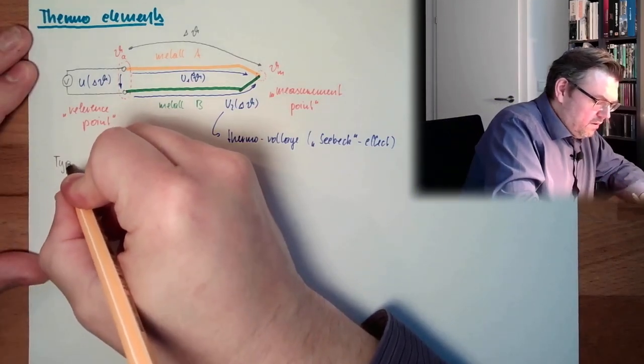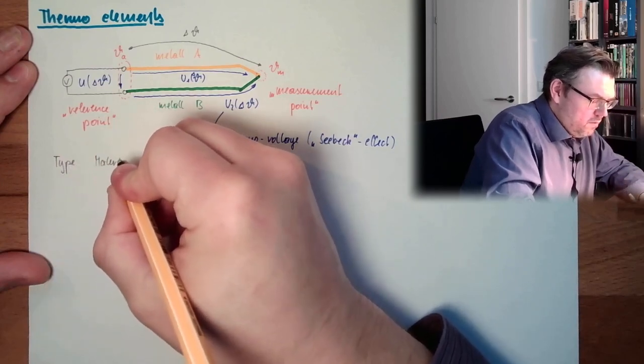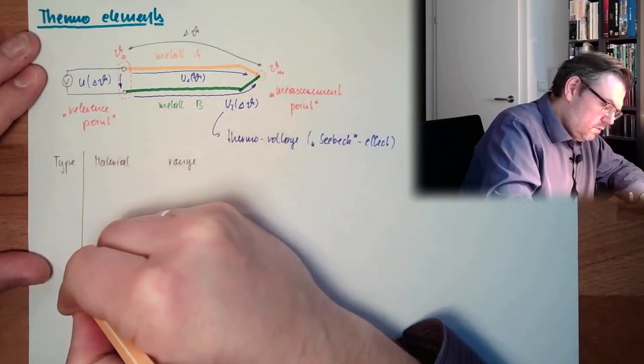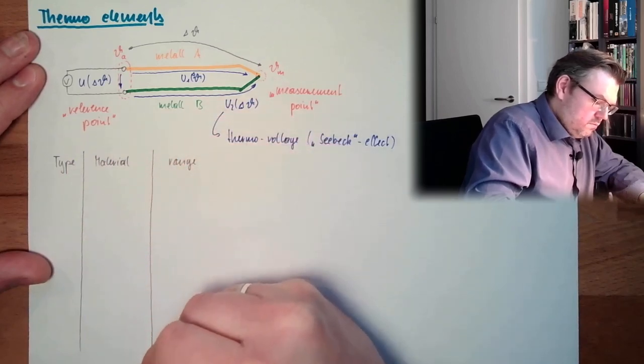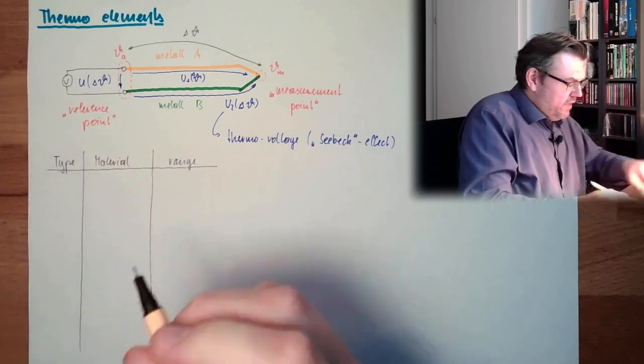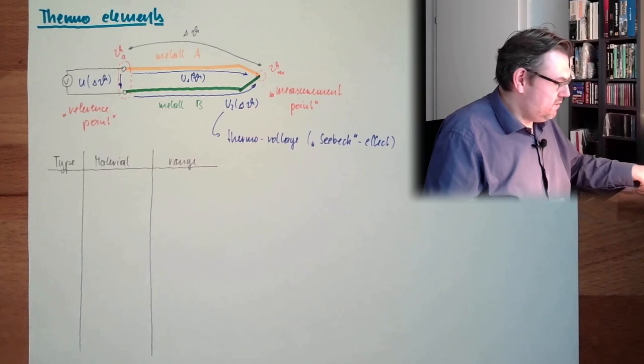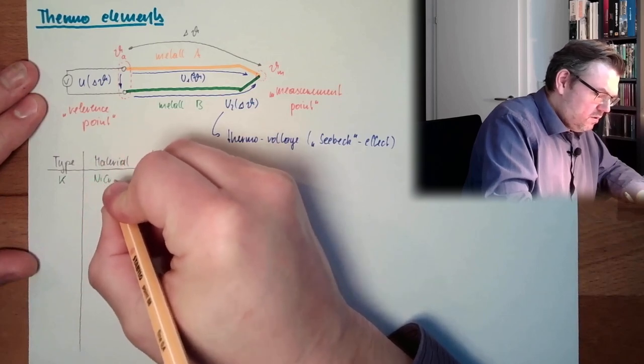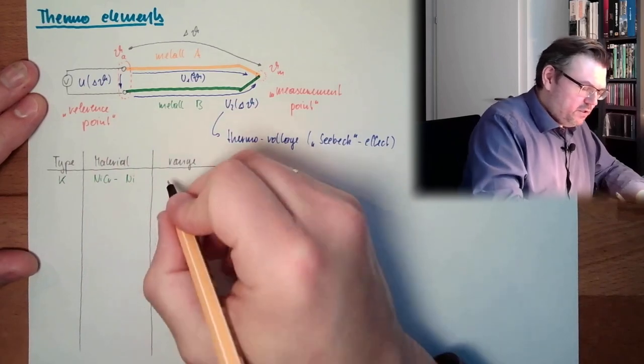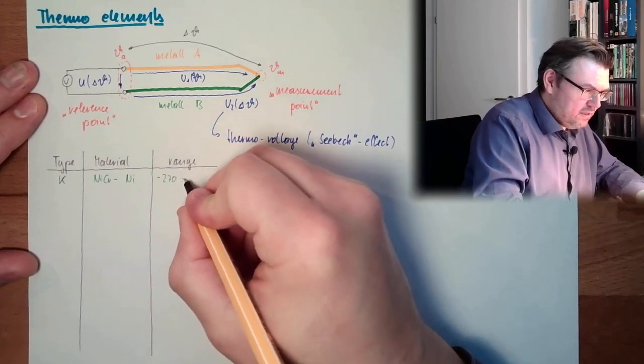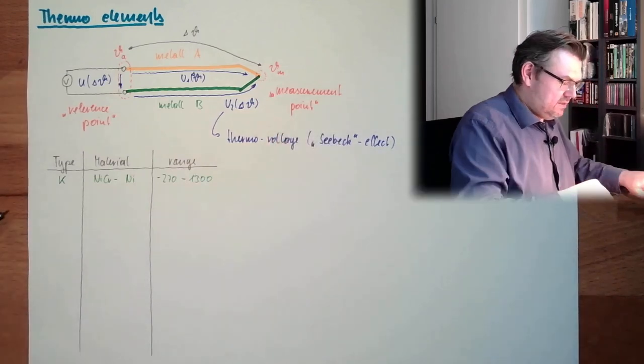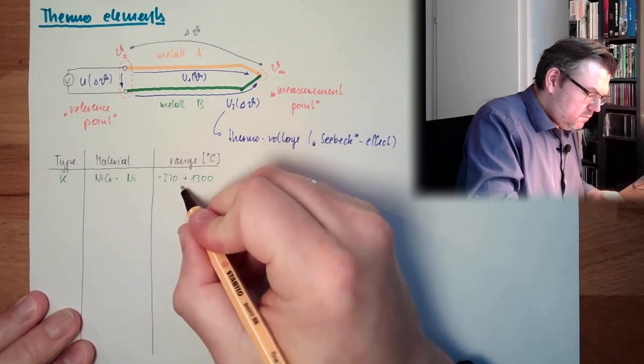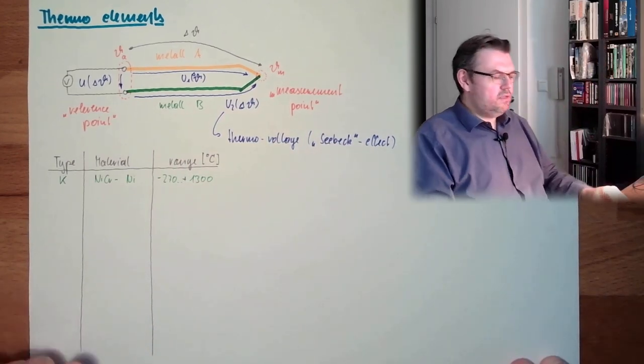And write it down, type, material, range. Very commonly used is the standard type K. This is nickel-chrome, chromium-nickel. And the range is between minus 270 degrees Celsius to 1300 degrees Celsius.